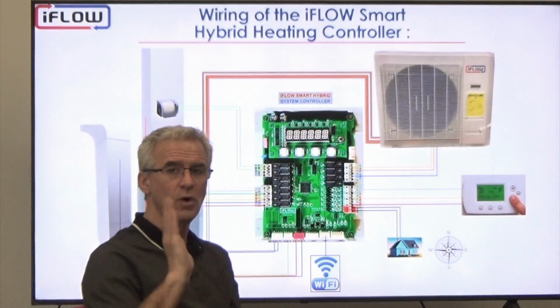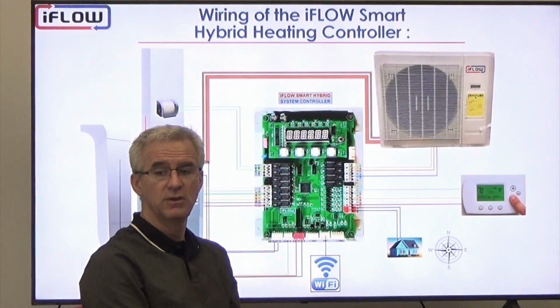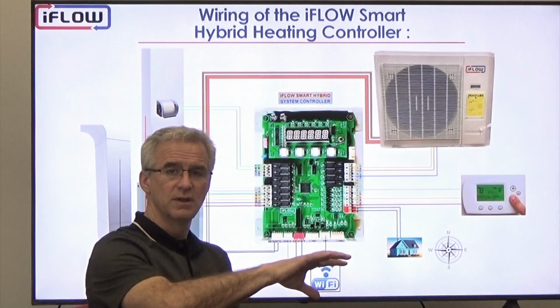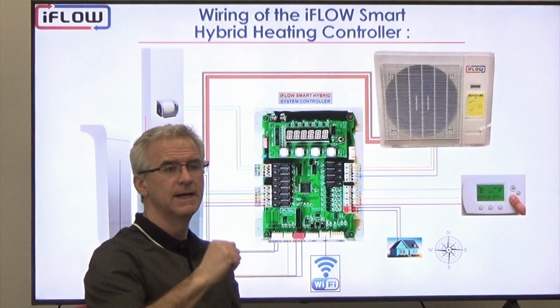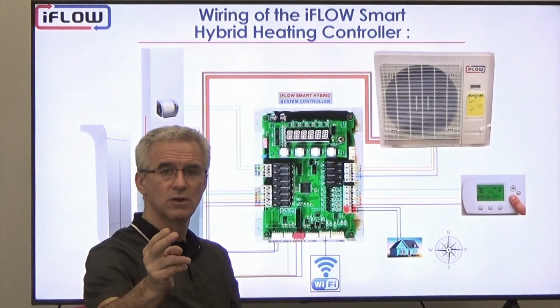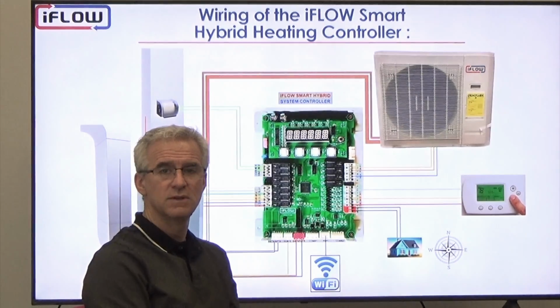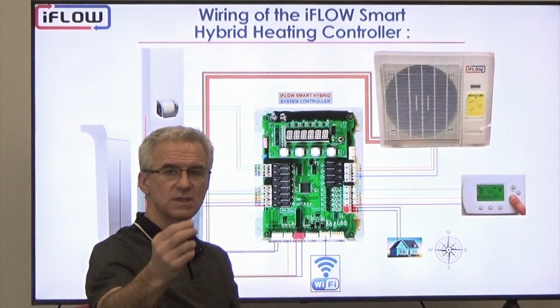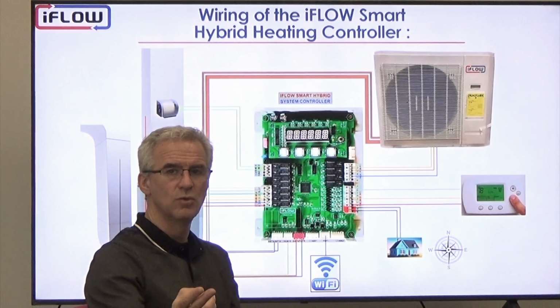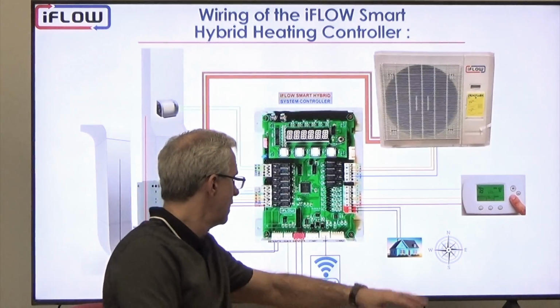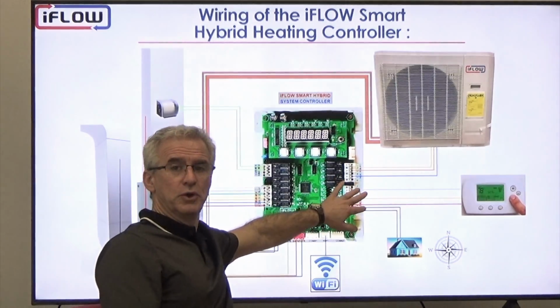If you're running new wire out to the heat pump, which you would typically do when you switch your old air conditioner out for a new heat pump, if they run 2 additional wires in that bundle out to the outdoor unit, you can always leverage off that and use those extra 2 wires to connect your sensor. So these would be our inputs.